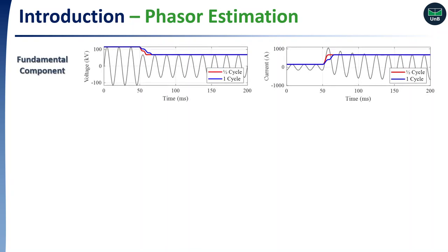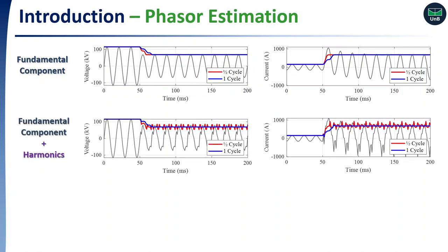For example, consider a fault that takes place in an AC system. Here we can see the AC voltage and current signals and the magnitude of the fundamental phasor estimated using full-cycle and half-cycle DFT-based algorithms. If we consider harmonic components also arise just after fault inception, we can see that phasor estimation using the half-cycle algorithm suffers from inaccuracy. On the other hand, there is no error caused by harmonic components when using full-cycle algorithms.